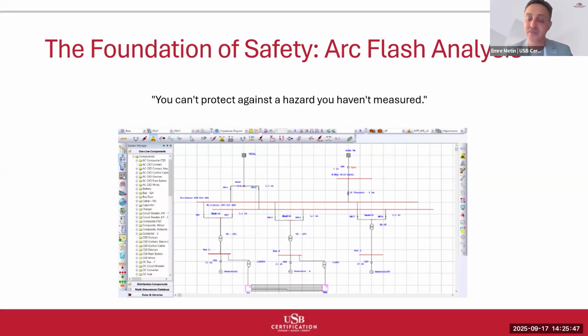NFPA 70E requires this analysis for systems operating above 50 volts. It means the touch voltage level in all international standards. It must be reviewed every 5 years and after major system changes. This isn't bureaucratic overhead. Electrical systems are dynamic. Equipment ages, loads change, protective device settings get modified, and new equipment gets added. What was a low hazard location 5 years ago might be high hazard today. The analysis provides two critical outputs: the incident energy level in cal/cm² and the arc flash boundary distance. These directly determine PPE requirements and safe working procedures.